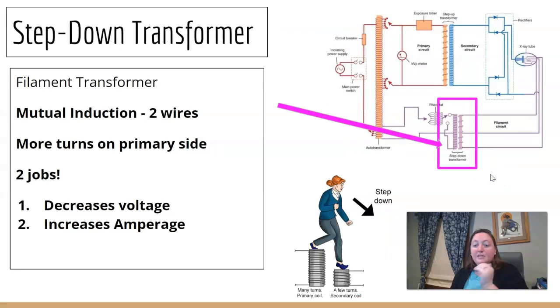And we're going to go down to the bottom one, the step down transformer. Again, two wires, mutual induction. It's going to decrease my voltage, but it increases my amperage. Sometimes this step down transformer is also called the filament transformer. If you think filament, thermionic emission, it's right next to my MA selector. They kind of go together. If you look at the windings here, there's more windings on the primary side than the secondary side. So we're stepping down.